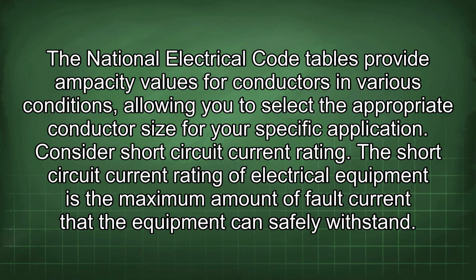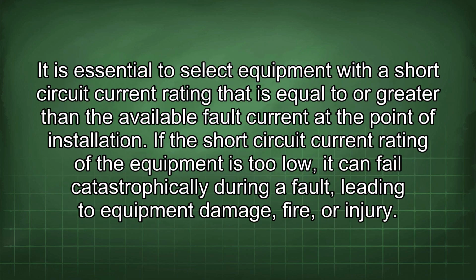Consider short-circuit current rating. The short-circuit current rating of electrical equipment is the maximum amount of fault current that the equipment can safely withstand. It is essential to select equipment with a short-circuit current rating that is equal to or greater than the available fault current at the point of installation. If the short-circuit current rating of the equipment is too low, it can fail catastrophically during a fault, leading to equipment damage, fire, or injury.